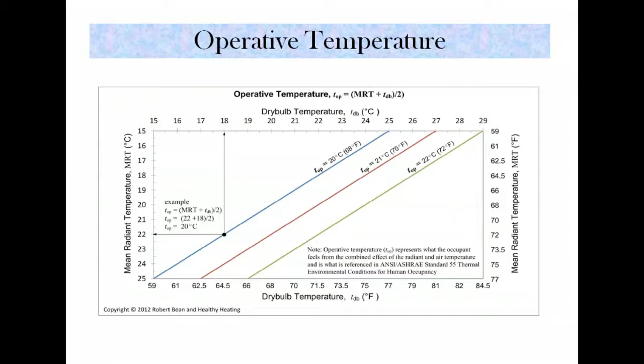Now, our human body generally rejects 47.5% of its heat in the form of radiant heat transfer. If a person is sitting in the room, in the heat load we generally consider the sensible load and the latent load from the human being. So 47.5% of the heat rejected by a human body in a space is in the form of radiant transfer, because the temperature of the human body is 98 degrees Fahrenheit, or 36.6, that is 37 degrees C, and we reject the heat to the surfaces of the occupied space, while 22.5% is in the form of convective heat transfer.